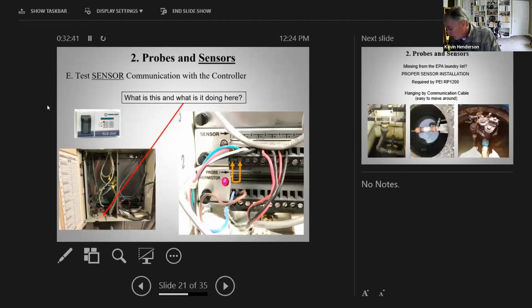And so the last thing I'll mention, and I almost hesitate to do this, but you just need to be aware of this. If you're an owner operator in particular, this is for you. If you have a service provider that's doing your annual operability testing and you see them opening up the console on your tank gauge, again, this is the 350, on the right side where the modules are and all the wires come in from the probes and the sensors, you kind of got to question, what are they up to? Why do you need to open this?